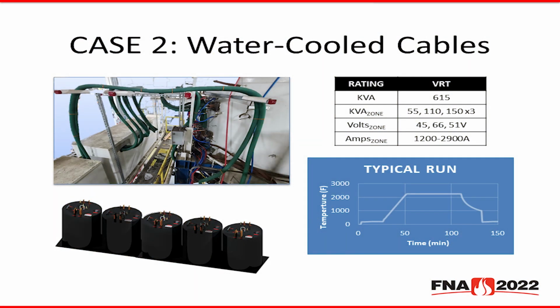So this leads us into our second example of an electrically underperforming furnace. Specifically in this case, we'll look at the effect of long water-cooled cables in a system. This is a 5-zone system rated at 615 kVA. This consists of 3 side zones at 150 kVA, 1 top zone at 55 kVA, and 1 bottom zone at 110 kVA. The cycle was run, which is shown here, and it consisted of a ramp up to and hold at 2200 degrees Fahrenheit.